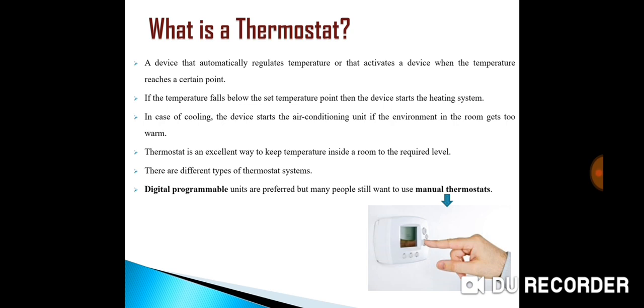Normally thermostats use different types of sensors to measure the temperature. In one form, the mechanical thermostat, a bimetallic strip in the form of a coil directly operates electrical contacts that control the heating or cooling source. Electronic thermostats instead use a thermistor or another semiconductor sensor that requires amplification and processing to control the heating or cooling equipment.